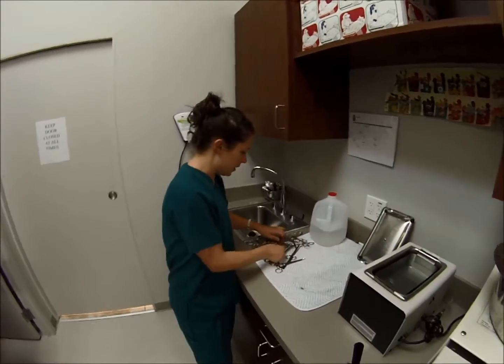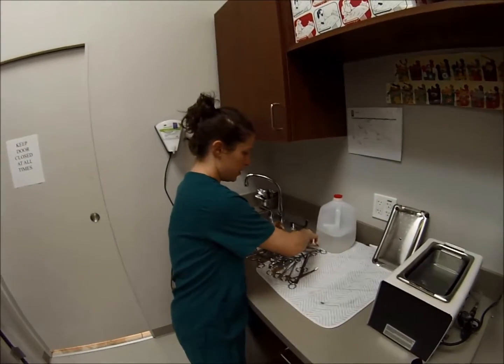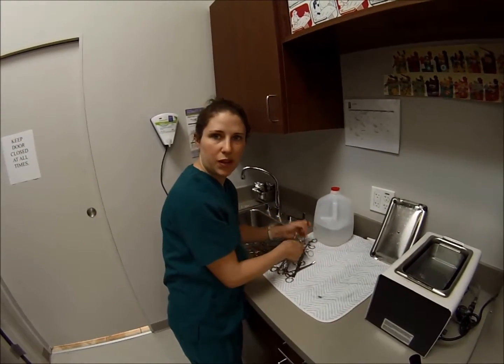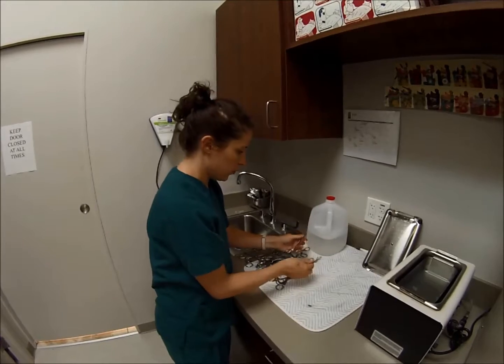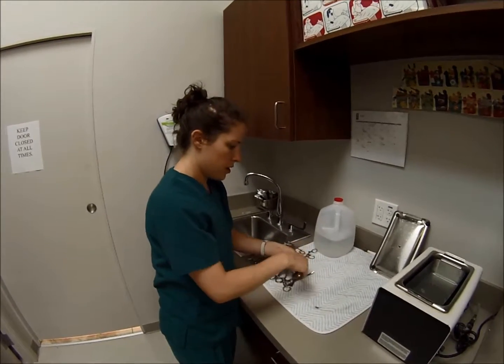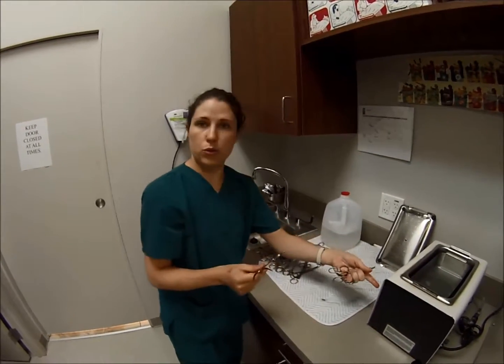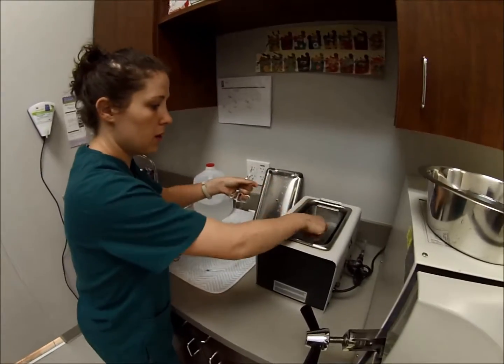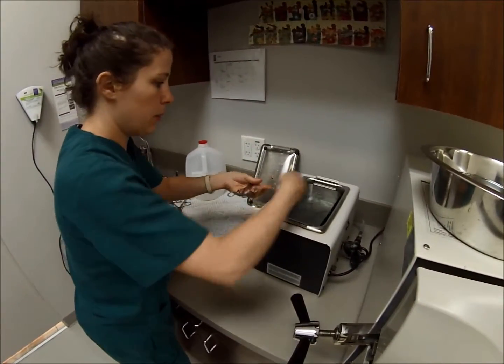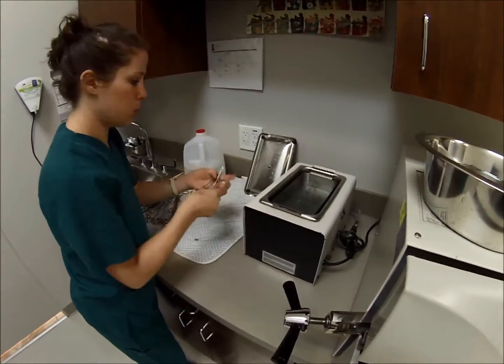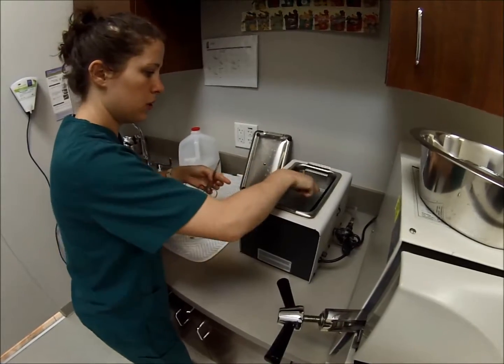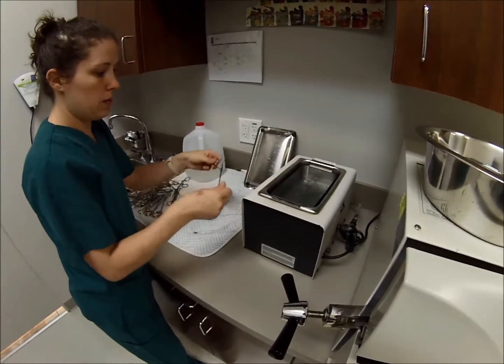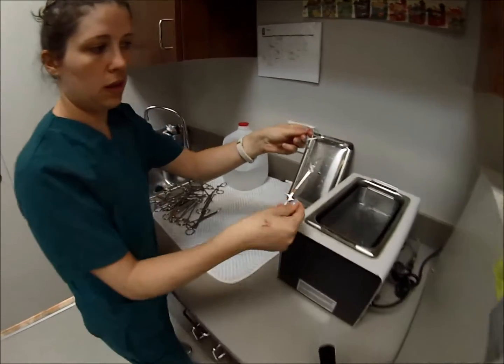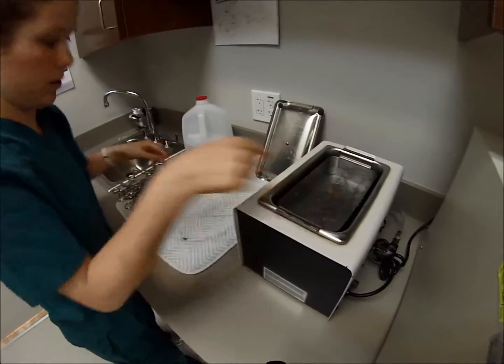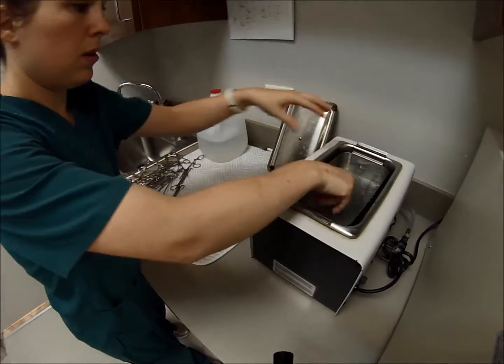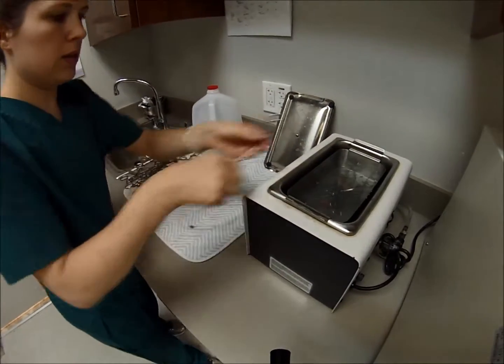So now that my instruments have been scrubbed, I didn't show the whole pack just because it's a pretty large pack, but I scrubbed and rinsed with my distilled water. Now I can begin loading them into my ultrasonic cleaner, which, like I said, utilizes tiny bubbles as a kind of scrubbing motion. It's called cavitation. When I'm loading my instruments in here, I want to make sure that the hinged instruments are opened. That way the bubbles can work their way into the grooves.